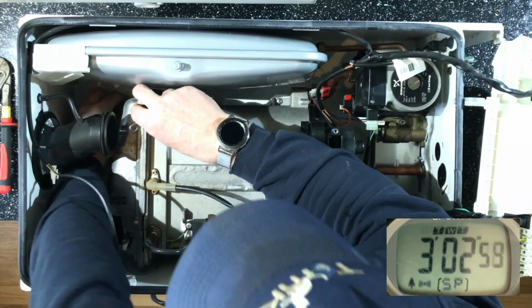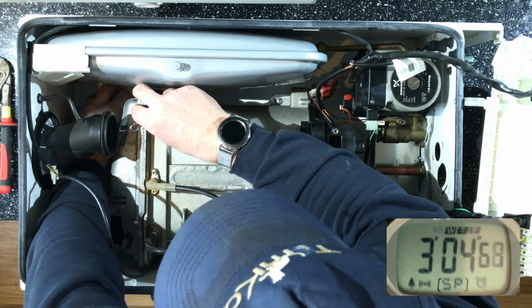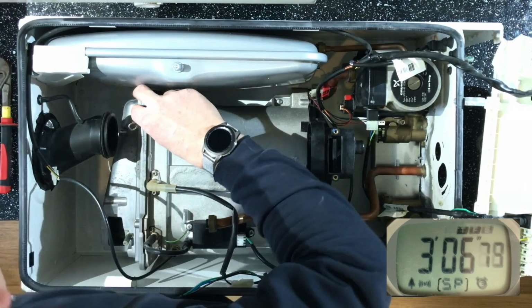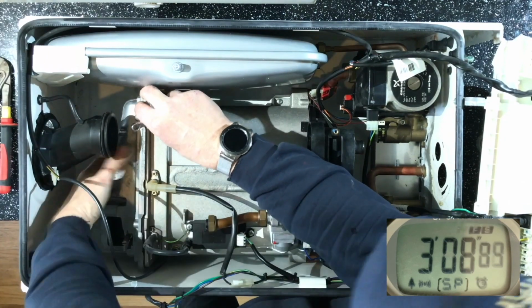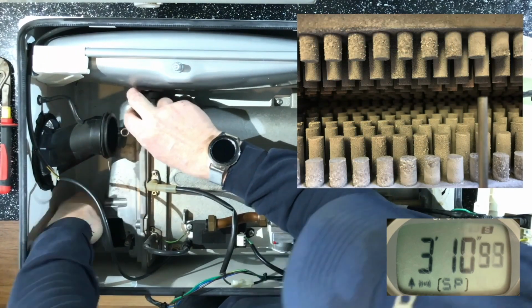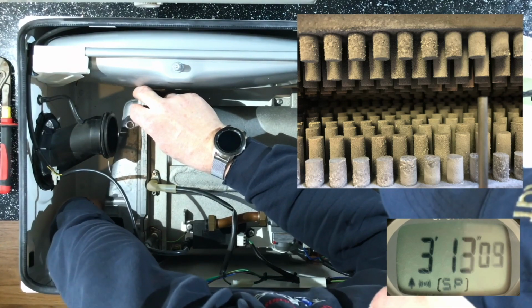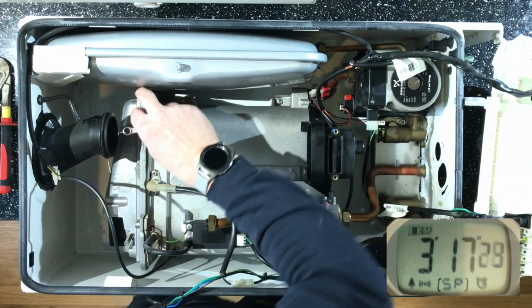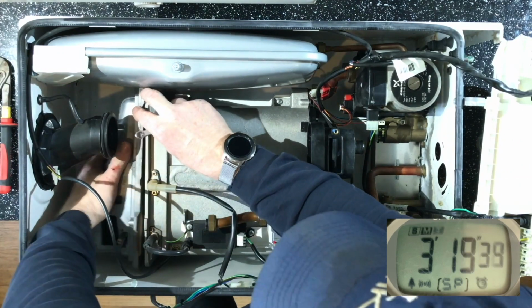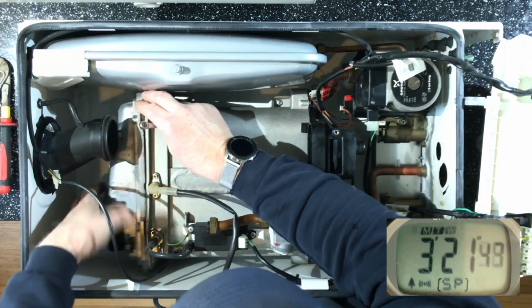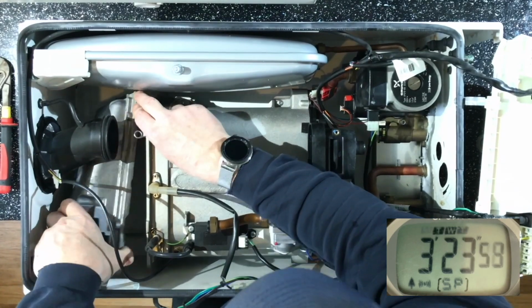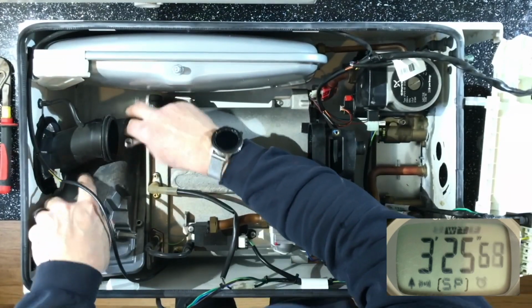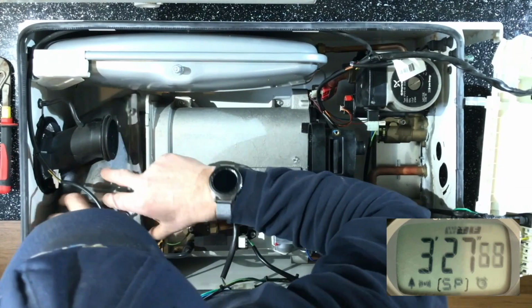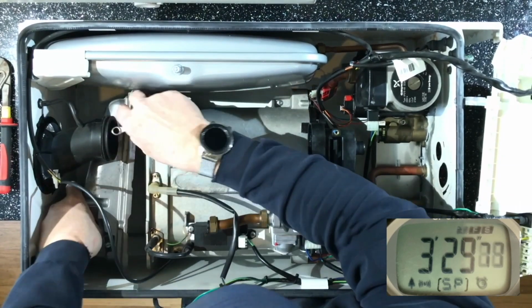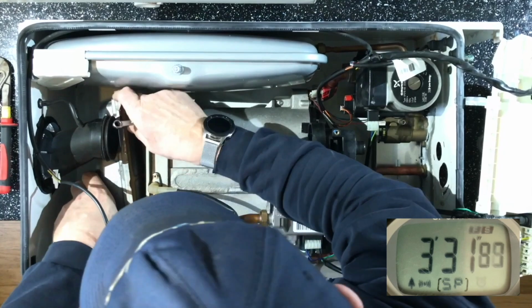So while I'm struggling to get this burner out, we will be seeing the heat exchanger. So the heat exchanger is constructed from cast aluminium alloy. The water enters via the return pipe connection on the right hand side of this heat exchanger, and then splits into two waterway passages. Each passage travels up and down the heat exchanger 9 times before again meeting on the flow outlet, which is on the left hand side at the bottom of the heat exchanger.